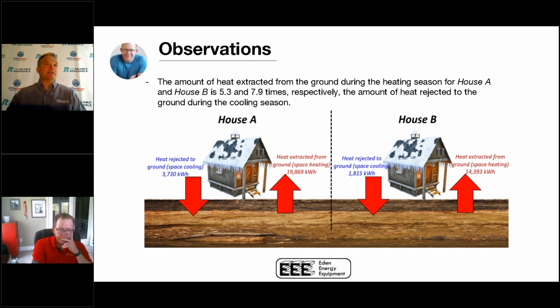We did a comparison of GeoLink, the design software that makes it simple to figure out how big your heat exchanger should be when you put the pipes in the ground. We compared that to the actual data used and the temperatures of the loop, and found that the software is within 5% accurate.